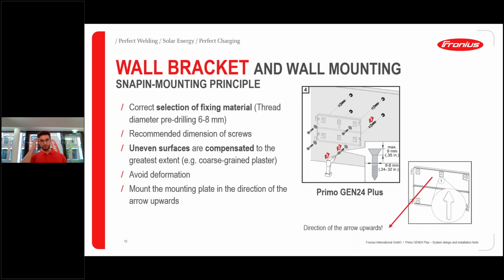Then we come to our first installation step, and this is to mount the wall bracket. It's really a lightweight wall bracket. It's just aluminum, and you fix it onto the wall or onto the plate where you want to mount it. You just select the correct fixing material, a minimum of 4 screws here, and just make sure that this small arrow on the bottom right corner is in the up position. Otherwise, we couldn't mount the inverter itself on it.